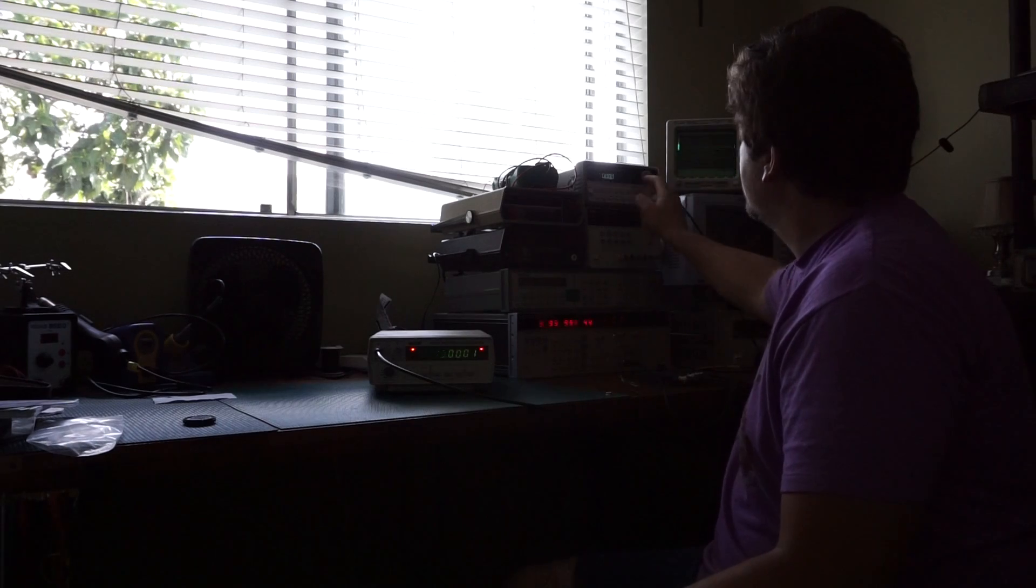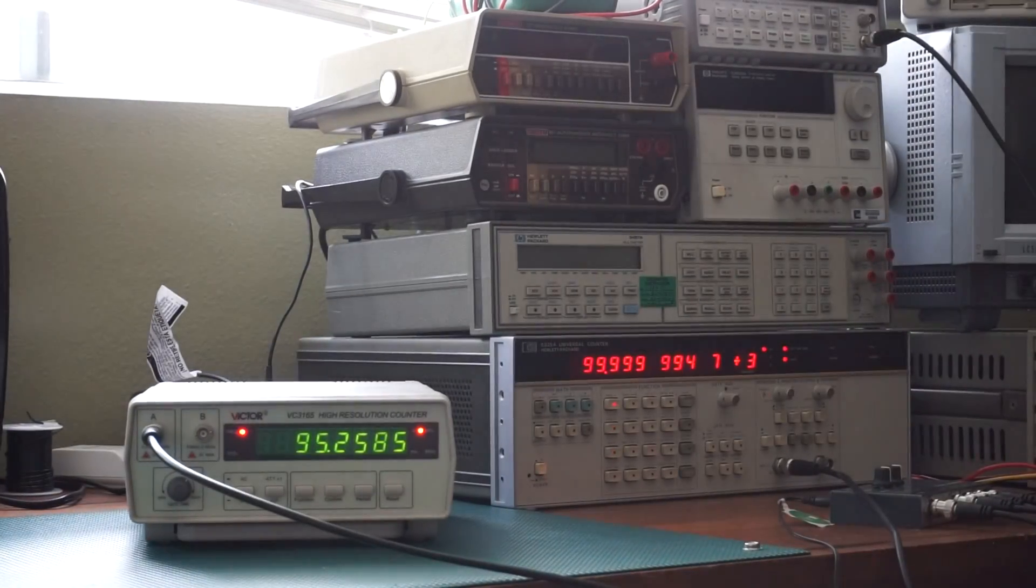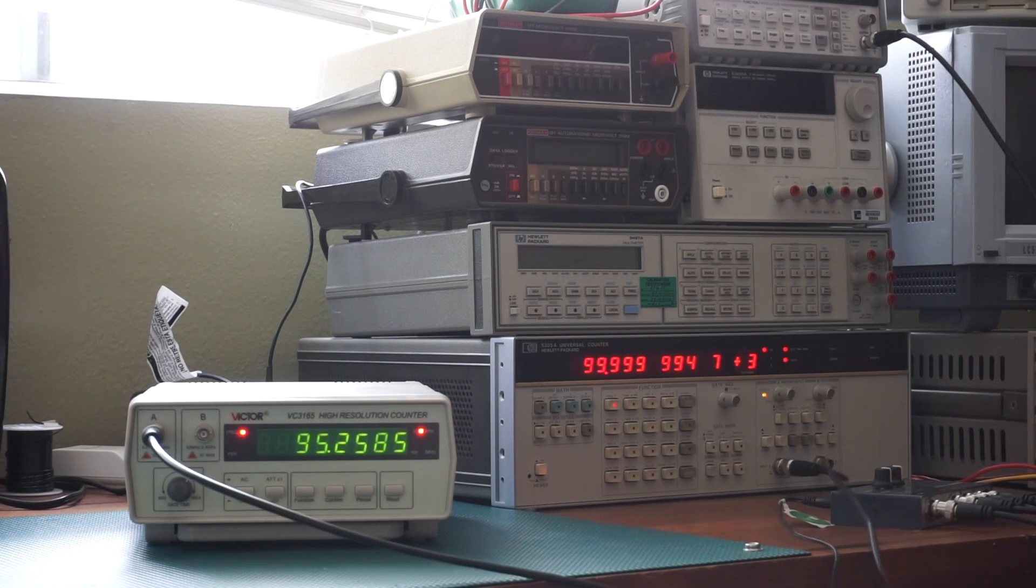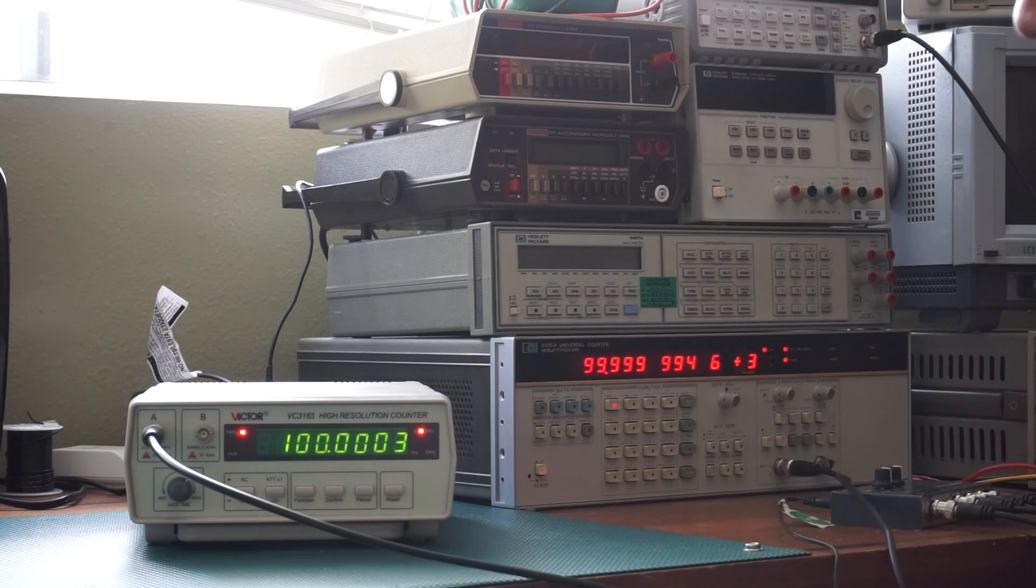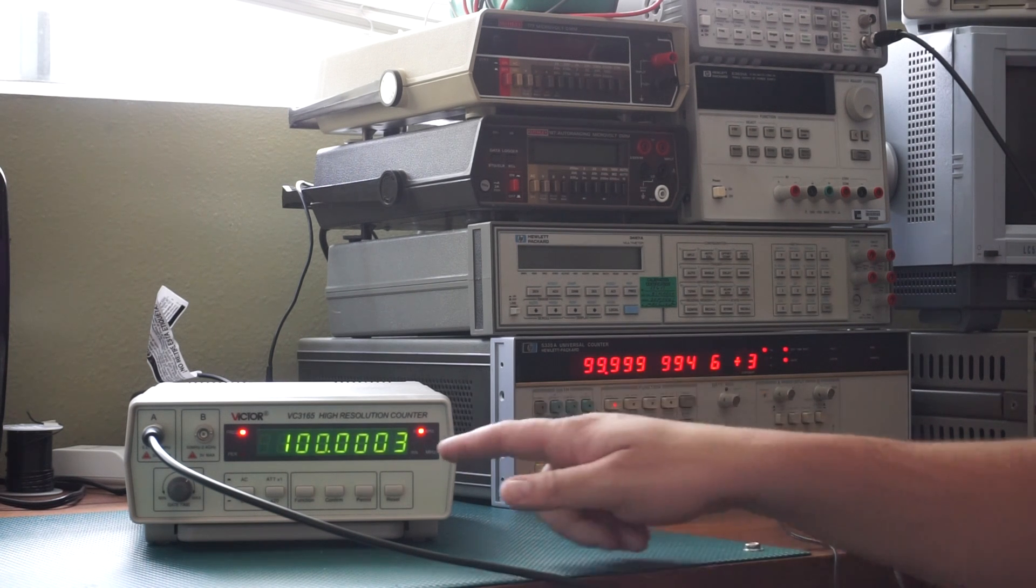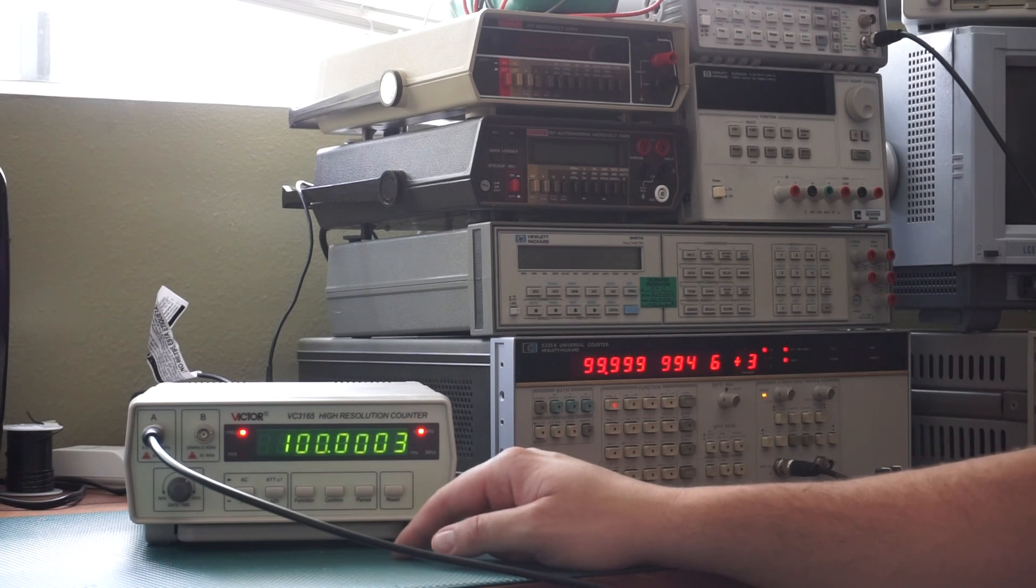Let's go to 100 kHz. Let's zoom in on this device here. As you can see it just now updated. That's how long the gate time is on it. It's pretty accurate. I mean at 100 kHz, maybe what, 3 parts per million off? Not too bad.